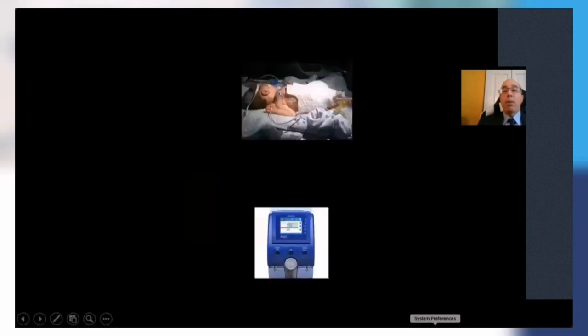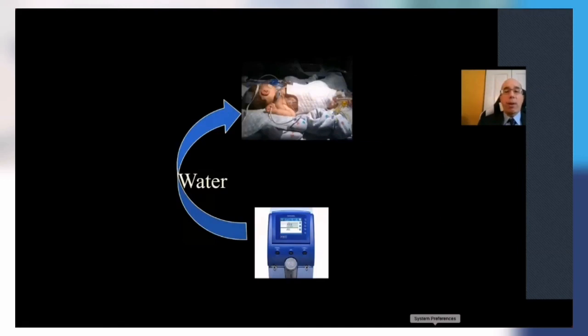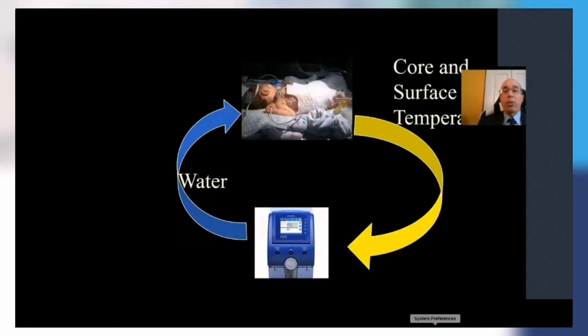Now, I wanted to talk a little bit about how this is done with the CritiCool, because we have to modify our normal technique when we do this in the MRI facility. So the way the CritiCool normally works is we set a desired temperature. It circulates water. It then measures the core and surface temperature from the neonate and makes any adjustments to the water temperature in order to maintain the core temperature within the targeted zone that we've dialed into the machine.